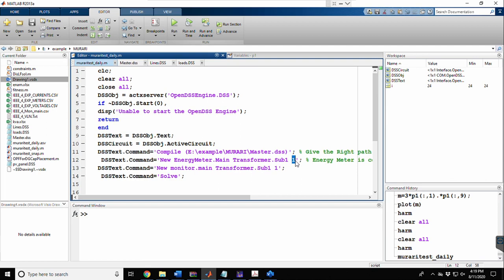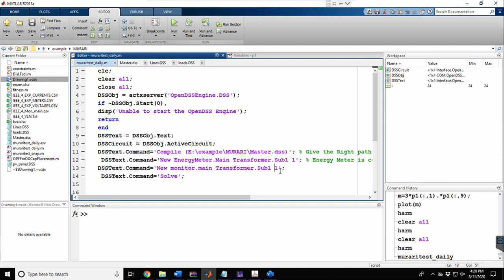If we write terminal 2 instead of 1, OpenDSS understands that the energy meter is connected on the secondary or low-voltage terminal. The second useful element is the monitor, which is essentially a prototype of an ammeter and voltmeter — it can measure current and voltages at each instant in the daily load flow. We create it using 'new monitor', name it 'main', and connect it to transformer sub1 at terminal 1.